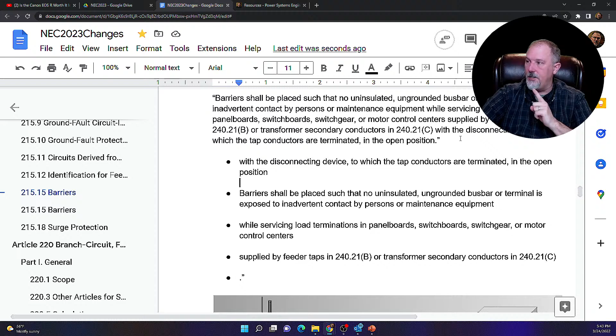Now, the only argument I could say is it says with the disconnect device to which the tap conductors are terminated. The transformer secondary conductors are not tap conductors. Those are transformer secondary conductors. Well, we should have said with the disconnecting device to which the tap conductors or transformer secondary conductors are terminated.